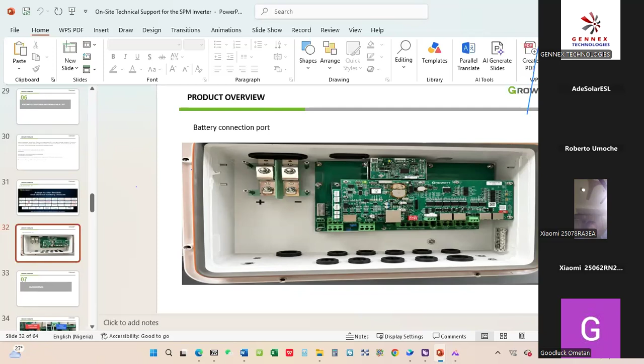It's on CN4 on the inverter. We connect the communication cable from the BMS of the battery to CN4 of the inverter. For our Growatt batteries, we mostly use PCS, so you connect it to the PCS port of the inverter. Then on the screen of this inverter, you do the settings. We'll see when we get there.